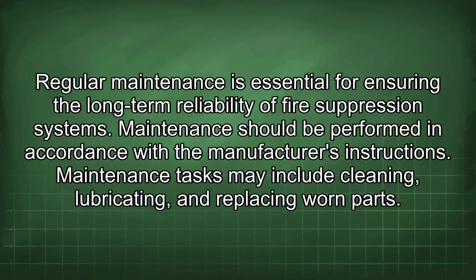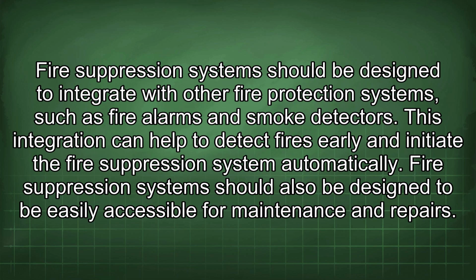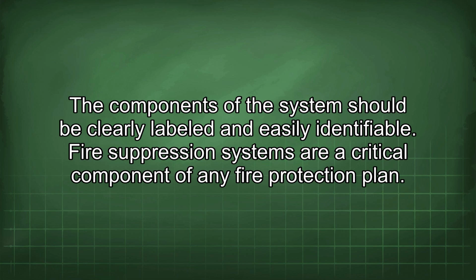Maintenance should be performed in accordance with the manufacturer's instructions. Maintenance tasks may include cleaning, lubricating, and replacing worn parts. Fire suppression systems should be designed to integrate with other fire protection systems such as fire alarms and smoke detectors. This integration can help to detect fires early and initiate the fire suppression system automatically. Fire suppression systems should also be designed to be easily accessible for maintenance and repairs. The components of the system should be clearly labeled and easily identifiable.